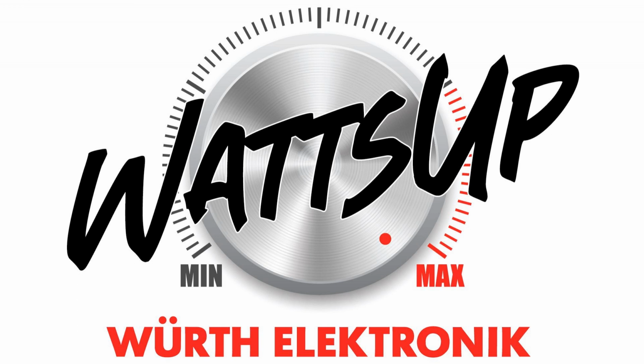I don't want to repeat the slides because Laurent explained it correctly, just to remind you of the effect of each component on the mode. The common mode choke acts on the common mode noise, while the capacitors act more on differential mode, especially the CX capacitor placed between line and neutral.